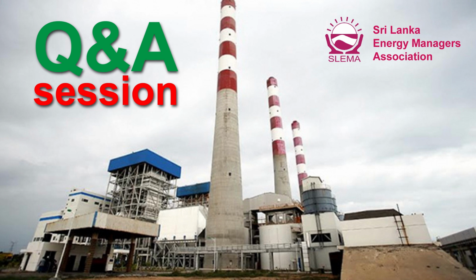Is it universal for all power plants to survive on house load only in a high frequency trip? Yes, of course. Apart from that, house load operation can work even when the generator circuit breaker opens itself for some other reason, not internal to the power plant. Of course, if there's a failure in the generator, you can't work with house load operation. So basically only in a high frequency trip, and of course df/dt as well, the rate of change of frequency on the high side.